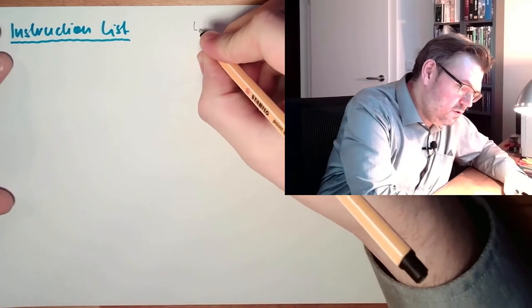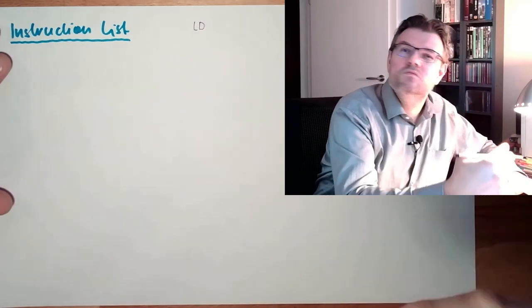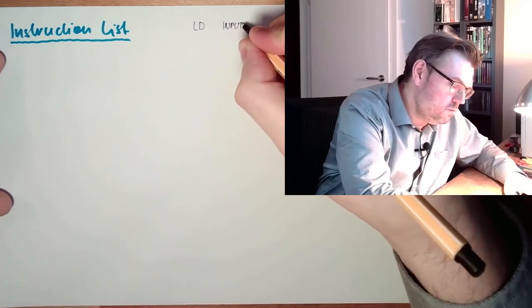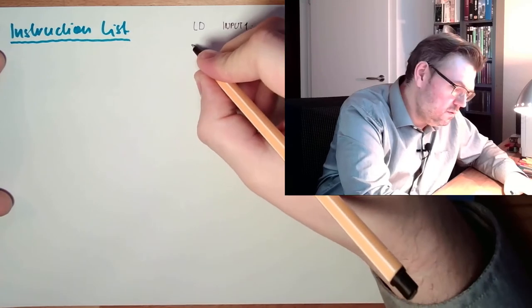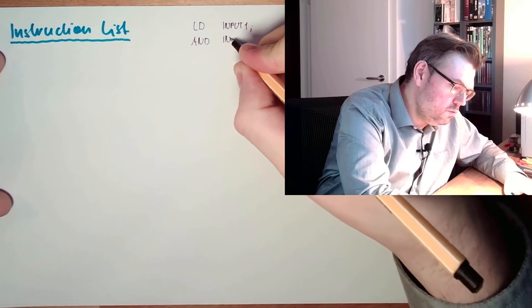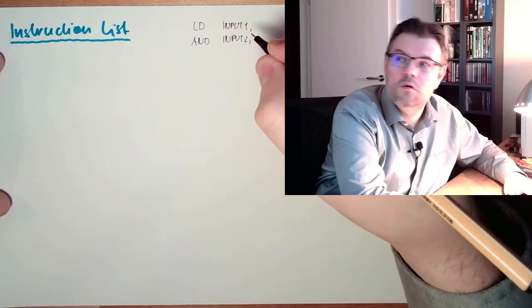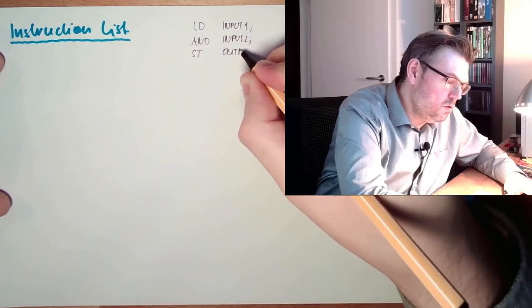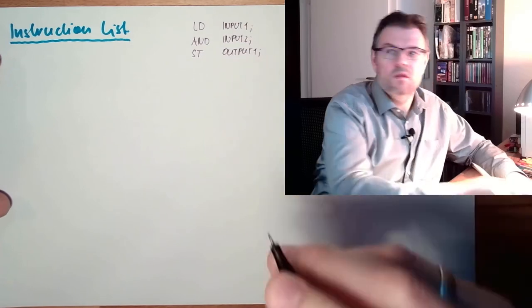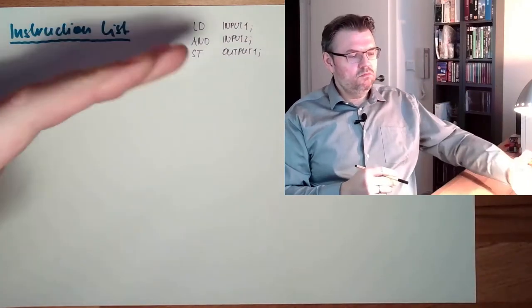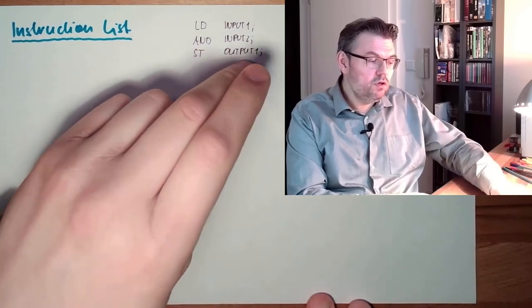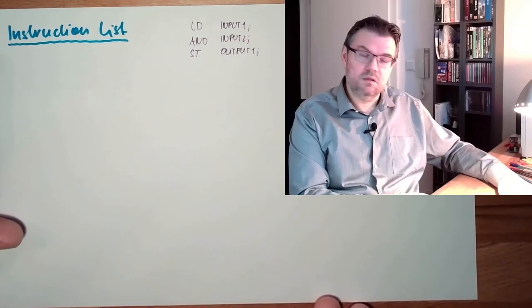That's it with Instruction List, very basic. Like a code would look like, for instance: LD - this is a command on one certain PLC type - input one, AND input two. Okay, ST for set output. This would be the command after I told you: load input one, make an AND with input two, and set or reset the output one to the result. The result is not even visible, so it's hard to read, hard to maintain, but usually very compact code.